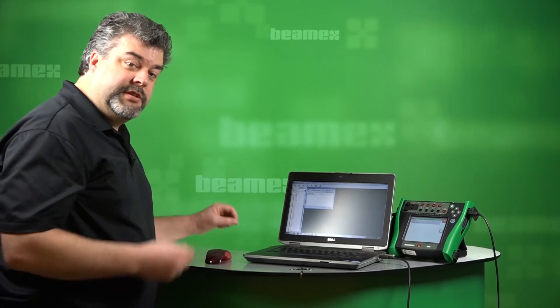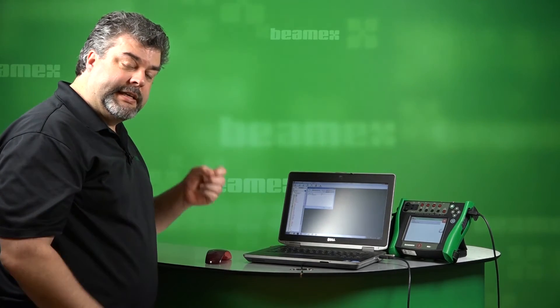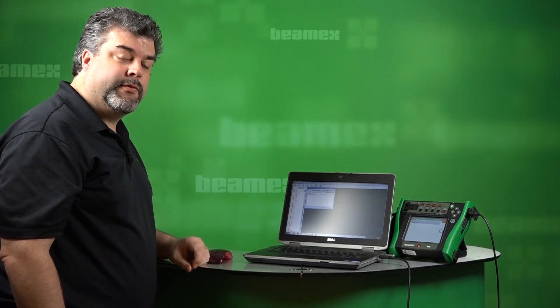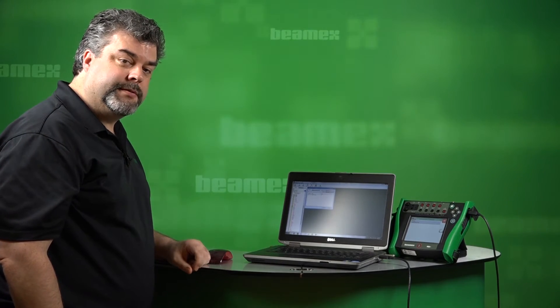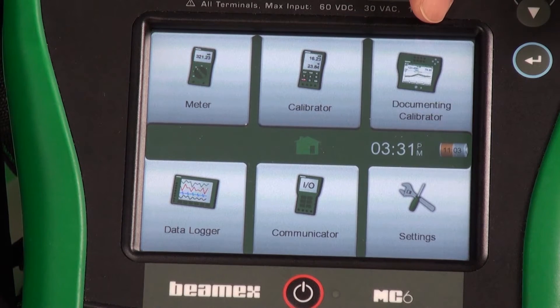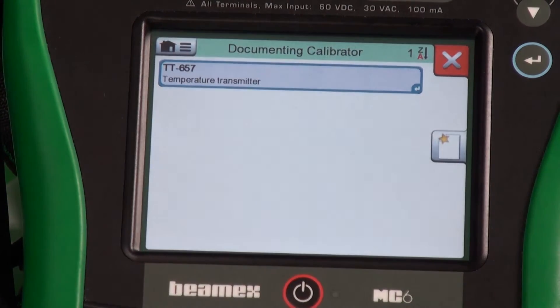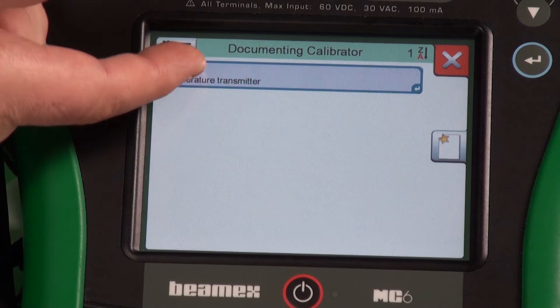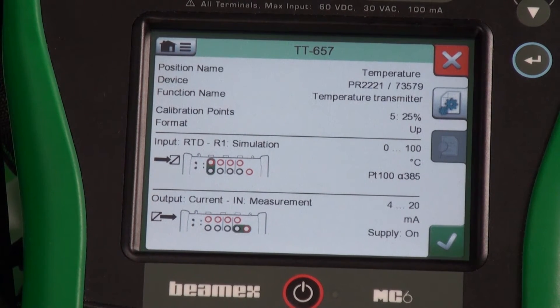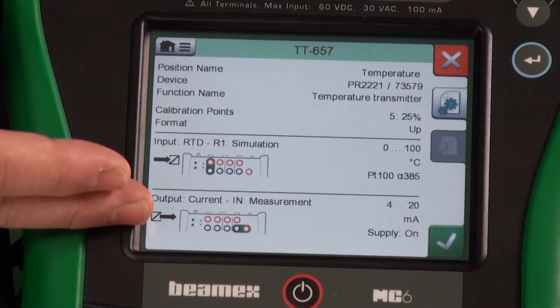At this point, we just disconnect the USB cable, take the calibrator out into the field, and perform our calibration. To start the calibration, we select documenting calibrator. We already have a test here that we've loaded from CMX calibration software previously. As a technician, this is my starting point, so I'll select the test itself, and this tells me all the parameters.